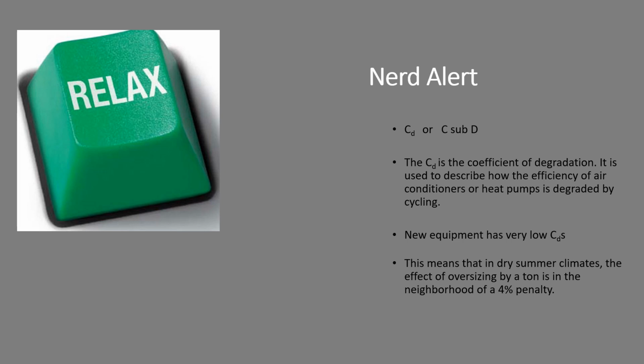So there's the nerdiest slide of today's presentation. It's called the C sub D, or coefficient of degradation. Newer heat pumps have a much lower coefficient of degradation. What that is, is the penalty you pay for short cycling. Newer systems, the penalty for short cycling, at least from an energy perspective, is not all that high.